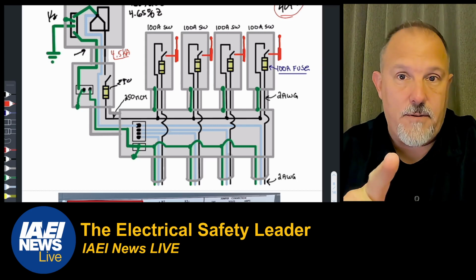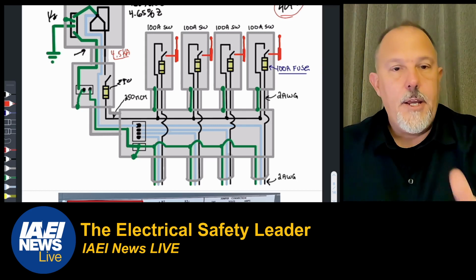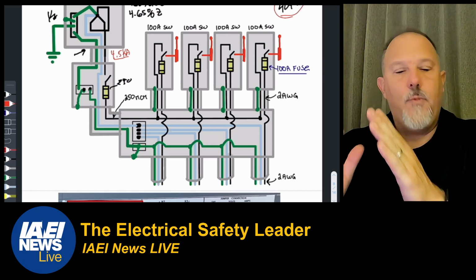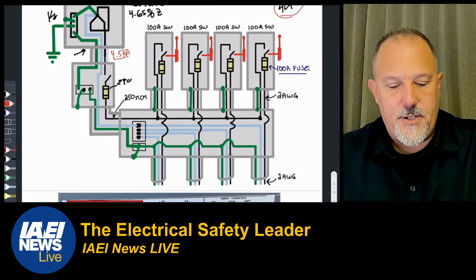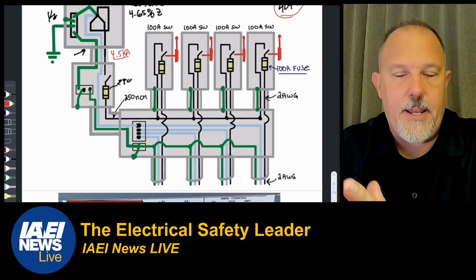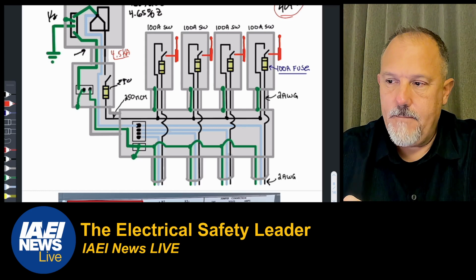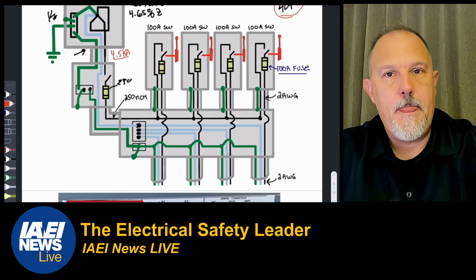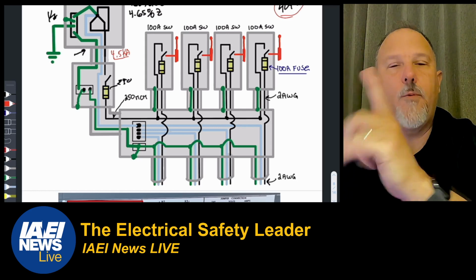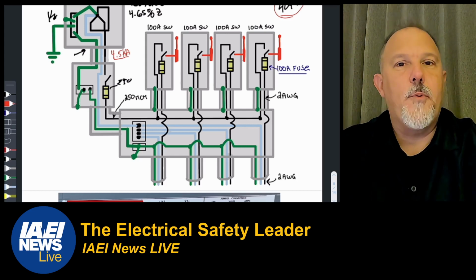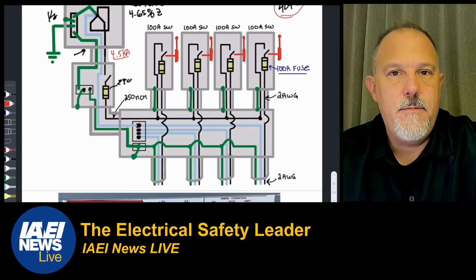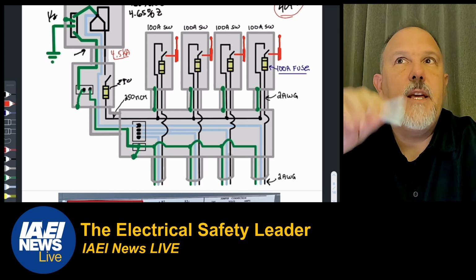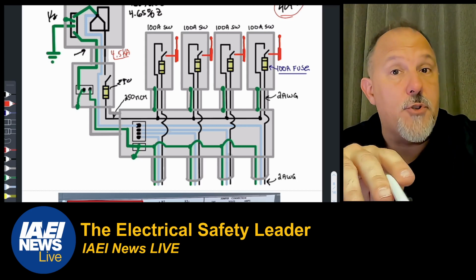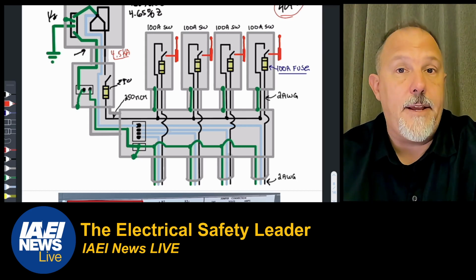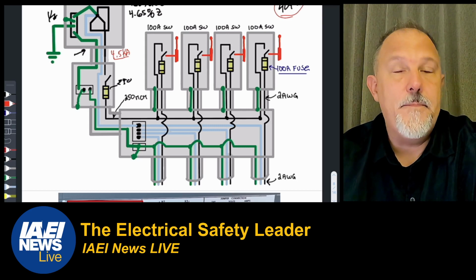Here was the concern. In residential applications, we were seeing switches. How do we do a light switch? We'd bring two hots down, break the circuit. We'd bring the equipment grounding conductor, but we wouldn't bring the neutral. We just switch the hot leg of the circuit.